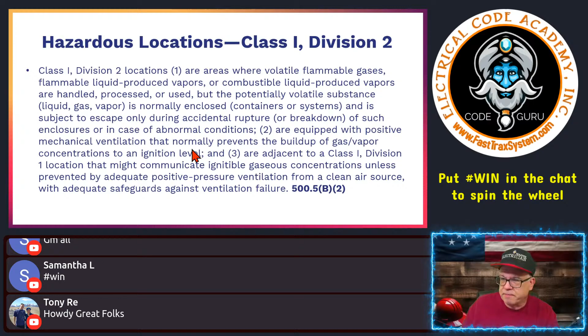ignitable gaseous concentrations unless prevented by adequate positive pressure ventilation from a clean air source with adequate safeguards against ventilation failure. So you could have a location that's right next to a Class 1 Division 1, and unless it has something that keeps it from getting from point A to point B, then you have an adjacent location without that precaution in place. Okay, no positive pressure ventilation, nothing, then all of a sudden you have a location that becomes a Class 1 Division 2 by proxy of its association with Class 1 Division 1. And that is covered in 500.5(B)(2).